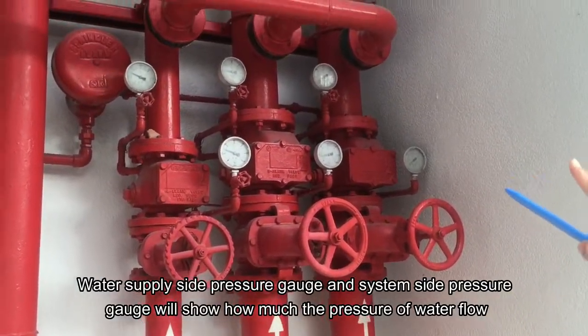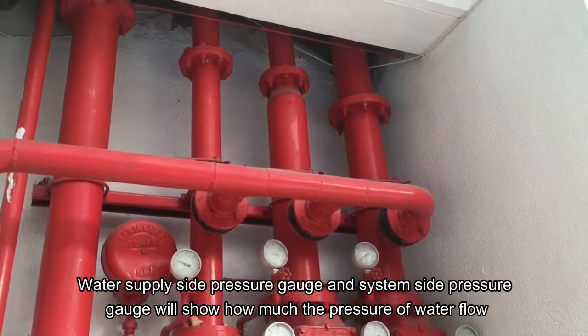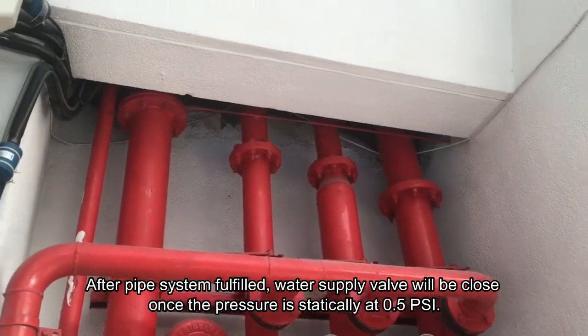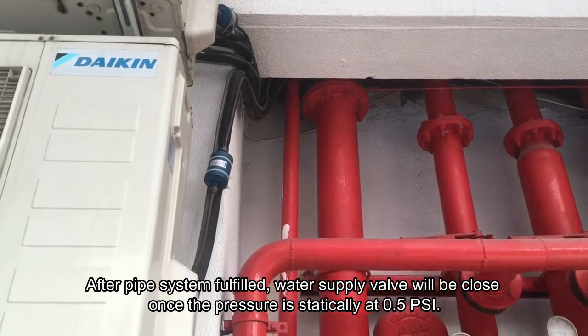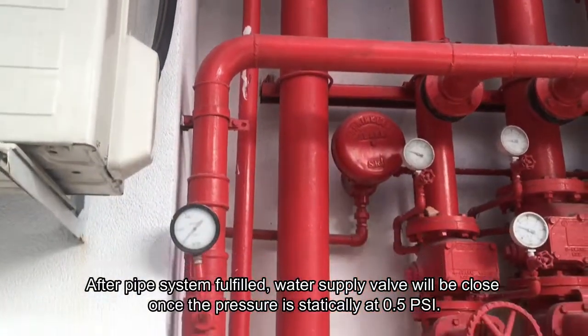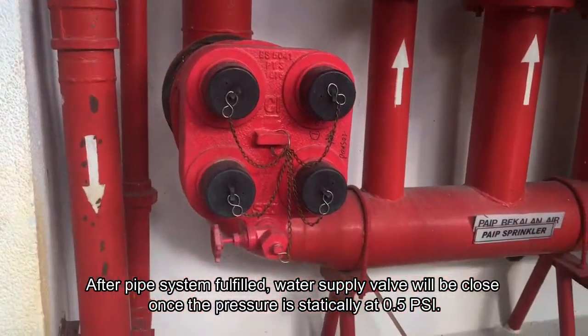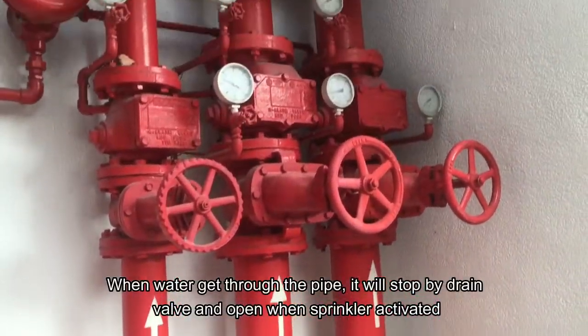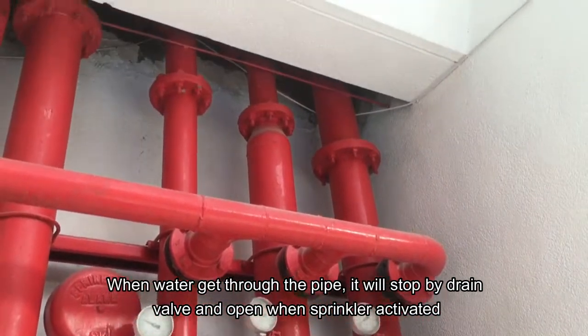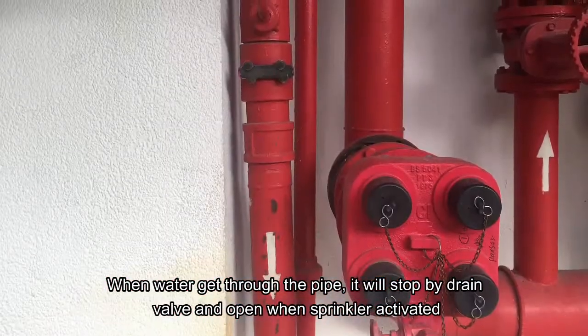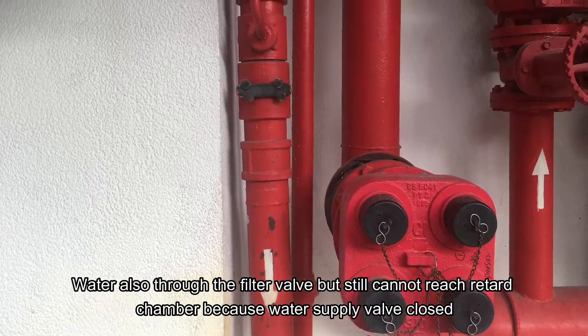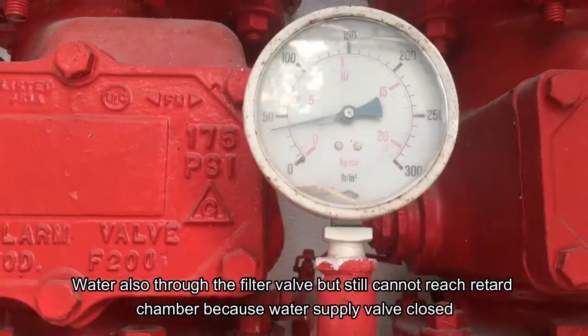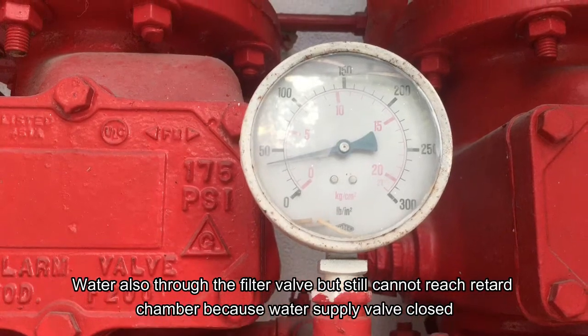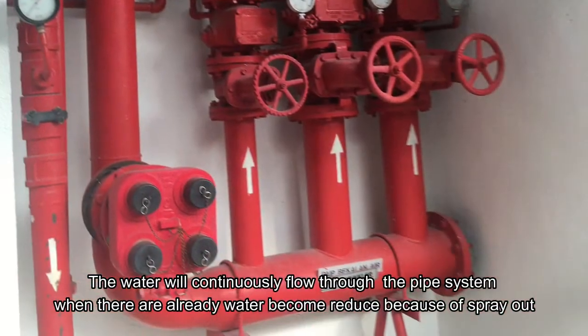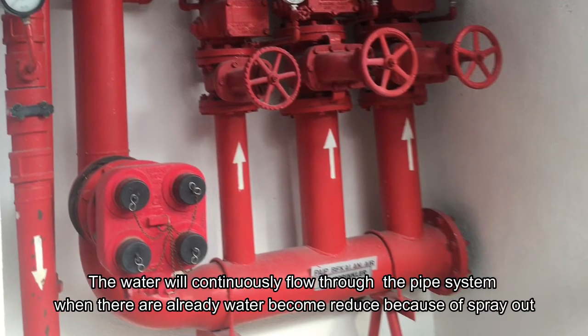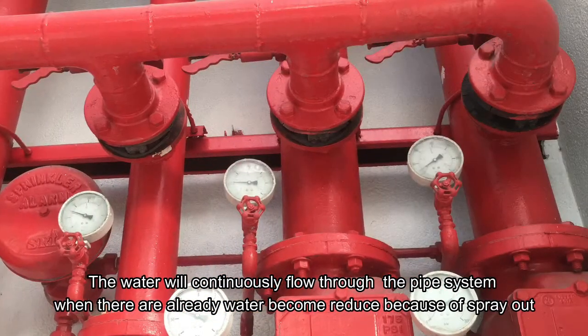The water supply side pressure gauge shows the pressure of the water flow. After the pipe system is filled, the water supply valve will be closed once the pressure is static at 0.5 psi. When water gets through the pipe, it will be stopped by the drain valve, which opens when the sprinkler is activated. Water also goes through the filter valve but still cannot reach the retard chamber because the water supply valve is closed. The water will continuously flow through the pipe system when the water is reduced because of spraying out.